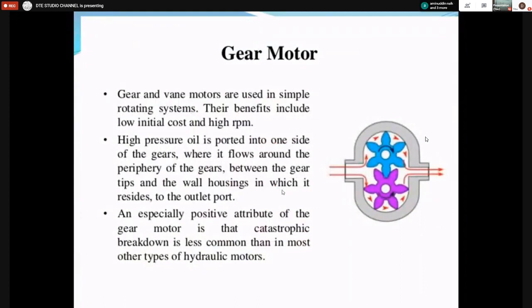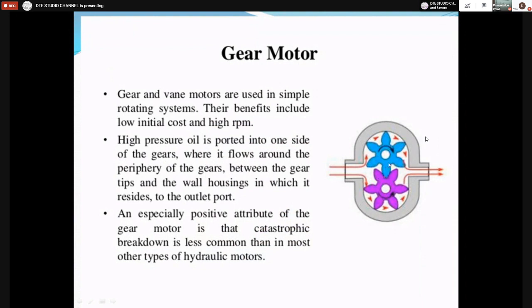Gear motors and vane motors are most commonly used. In gear motors, fluid enters at high pressure at the inlet and while passing between the gear teeth and the periphery of the casing, pressure gradually decreases from inlet to outlet, and the difference of pressure is converted into mechanical rotary motion. There are two gears meshing with each other, and there should be no clearance between them — otherwise fluid flows directly from inlet to outlet.